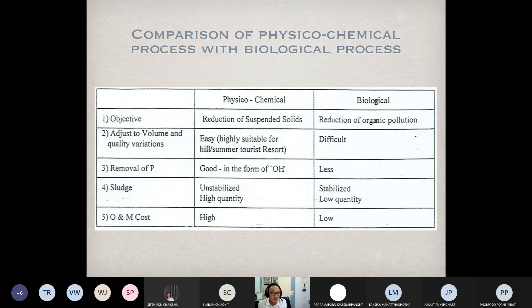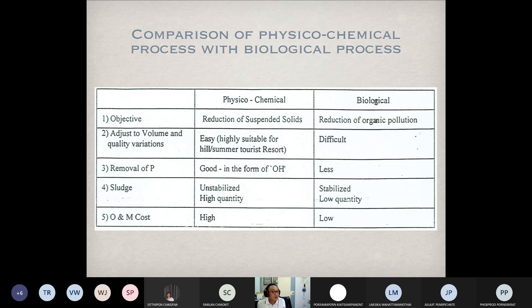In dry seasons, turbidity in water is low, but in wet seasons there may be landslides in upland areas, causing turbidity to increase. If turbidity increases up to 3000 NTU, we have to add more chemicals. But if turbidity is only 40 to 50 NTU, we just reduce the amount of chemicals. So in terms of volume and quality variations, physical-chemical treatment is easy to adjust.